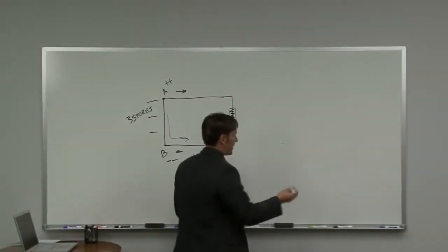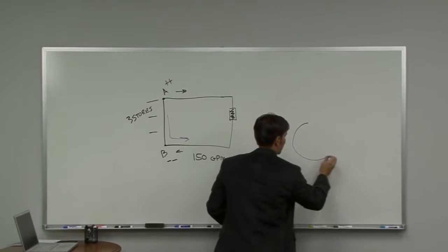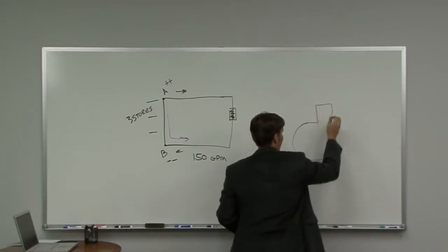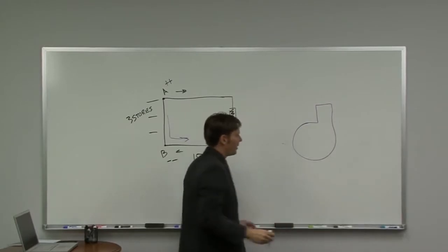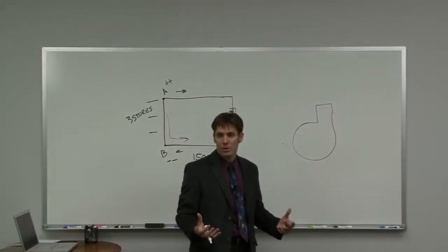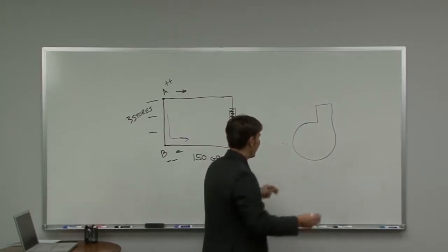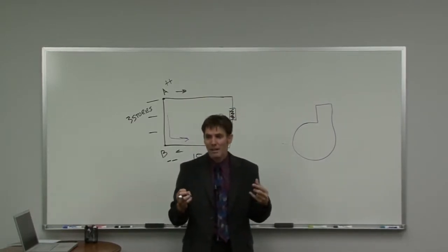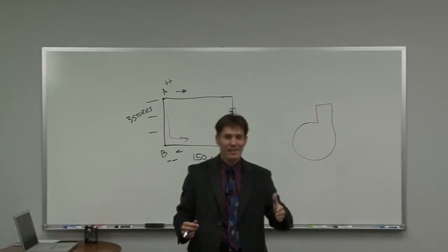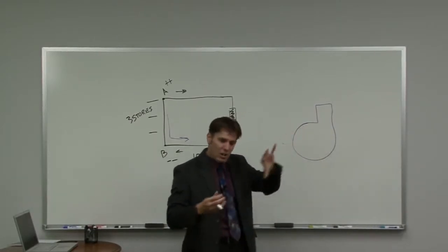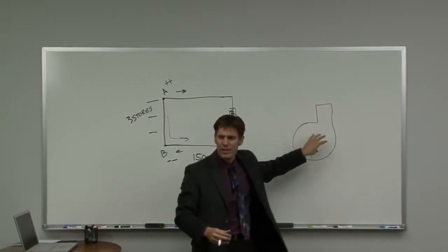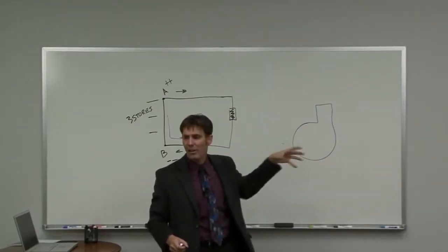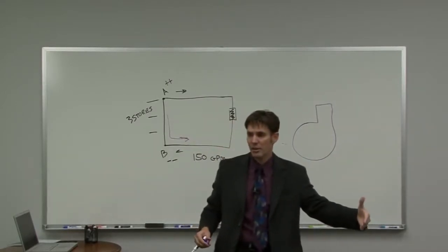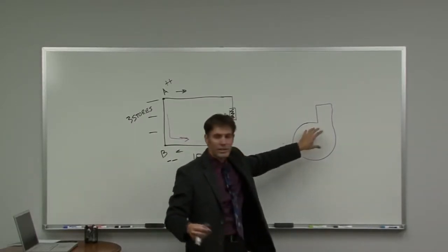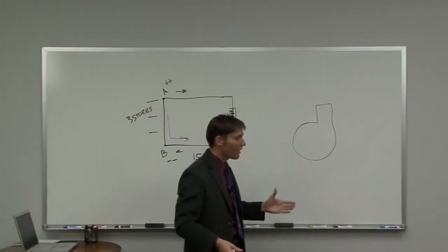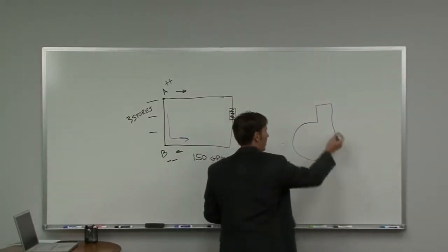Before we move on to selecting pumps, I do want to talk about that impeller. Let's define these terms. If I have a can inside of a can, this external can would be considered my pump volute, or the pump body. The volute is hydraulically designed by the manufacturers. Patterson Pumps is going to design their hydraulics, the inside curvature and the roughness and everything else inside this is going to define how their pump is going to work compared to a competitor. So they designed this in their R&D, their research and development, while they're building a product. They're running this through the design. So they hydraulically designed this.